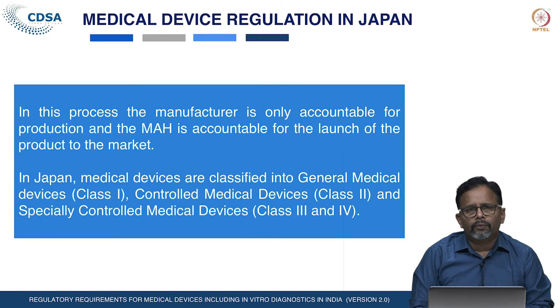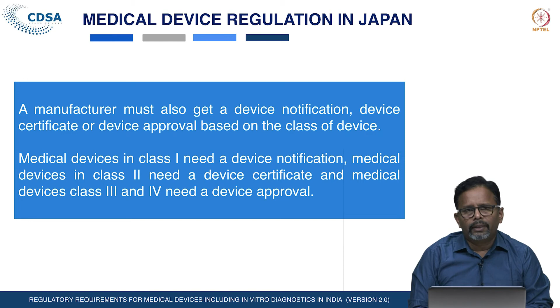Also in Japan, the devices are classified based on risk, and a four-tier system is there for classification of medical devices: class 1, class 2, class 3 and class 4. Class 1 devices are low risk devices and class 4 are high risk devices. Class 1 devices need notification; no approval from PMDA is required. Class 2 devices need device certificates, and class 3 and class 4 need device approval from PMDA.